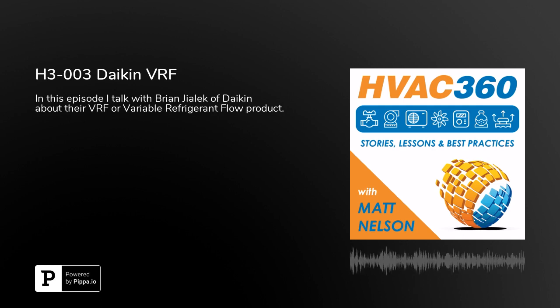Now, it varies wildly once you get into the heat recovery side because every company has its own way of doing it. Some manufacturers use one centralized big box that controls all of that function for the heat recovery function, and then some use individual boxes like us. It just depends which brand you pick. Okay, but again, the only reason that you'd need the heat recovery is if you had that need for simultaneous heating and cooling. That is correct. Okay, that you're going to end up paying a premium for, obviously. Absolutely, with any brand. Exactly.